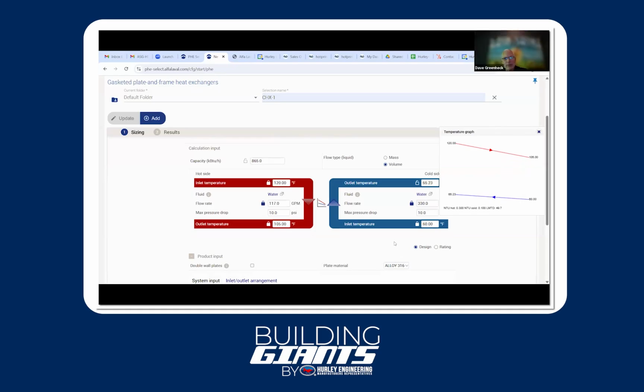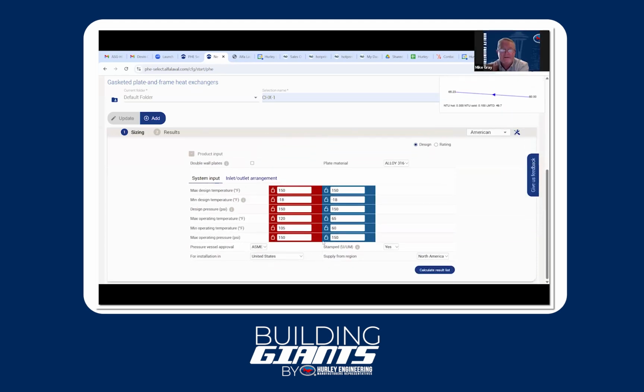We have one more question: what are the upper temperature limits? It's really driven by the gaskets, I want to say - is that right? Yes, it is. Here's where you change that if you've got higher temperature limits. You want to change that here, and that will directly affect the gasket material selected, and possibly the plate material depending on the temperature, but most likely the gasket material.